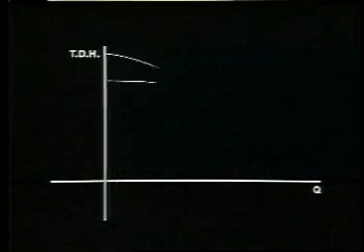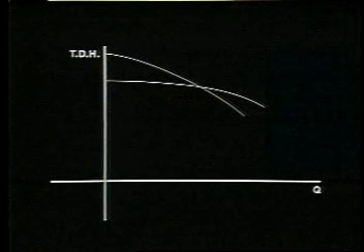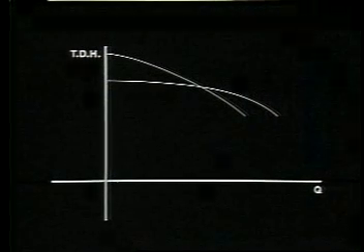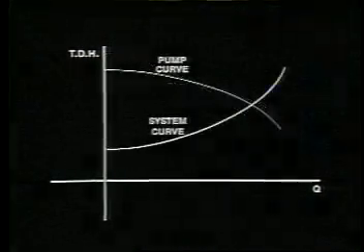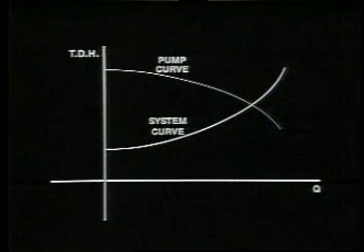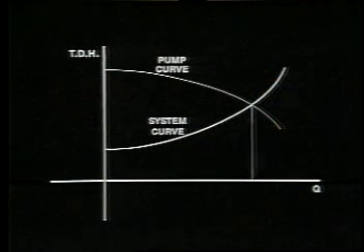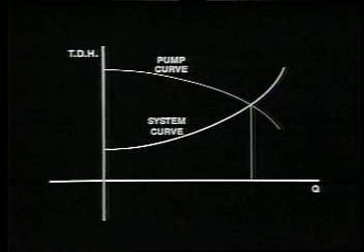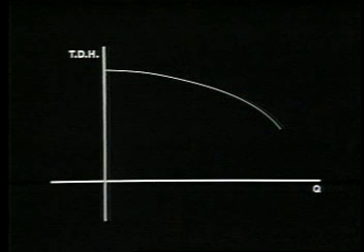Different pump designs produce different slopes of the pump curve, as well as the extent of the capacity and head which the pump can develop. To determine if a pump is suitable to operate in a particular system, the pump curve must be superimposed on the system curve. The pump will operate only where the pump curve intersects the system curve. When a pump is installed in a system, the impeller diameter and its speed of rotation are rarely changed, so the pump performance curve remains stable.